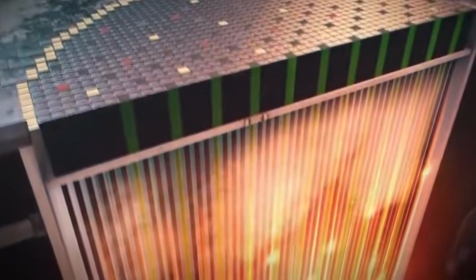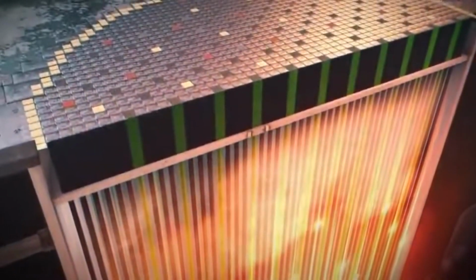Safer reactors of other designs use water both as a coolant and as a neutron moderator. The use of water as a moderator has allowed for better control and has prevented similar accidents, as well as making the active zone much smaller. When water is converted into steam, its ability to moderate neutrons decreases and reactivity drops. Higher enriched uranium is used for these reactors. Graphite was considered the best moderator due to the ability to use cheap low-enriched uranium. The transition to water occurred when improved uranium enrichment technologies allowed for its production in sufficient quantities.